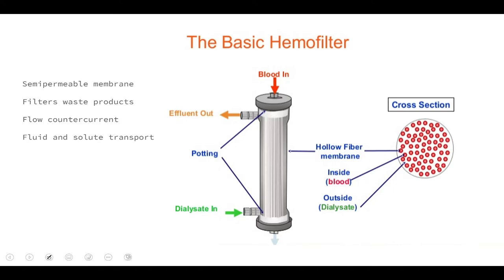Let's take a look at the hemofilter — probably the most important part of the CRRT machine. It filters waste products by creating a semi-permeable membrane between the dialysate and the blood. If you take a cross-sectional view of the hemofilter, you'll see what looks like little straws filled with blood, surrounded by dialysate solution. Within the permeable membrane of those straws is where the exchange of waste products and electrolytes takes place, through diffusion and hemofiltration.